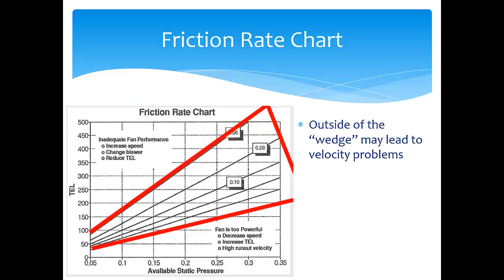First, we need to make sure the friction rate we calculated fits into the friction rate wedge. On this graph, the x-axis represents the available static pressure, the y-axis represents the total effective length, and the diagonal lines represent different values of the friction rate. Since we calculated a friction rate of 0.096, we can see from the graph that it falls within the desired wedge. Above the wedge means a fan that's too weak; below the wedge means the fan is way too powerful for our needs.